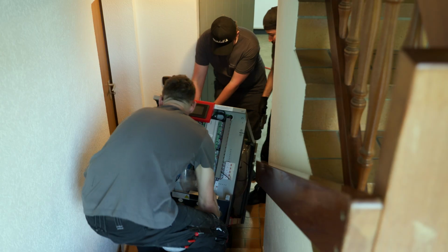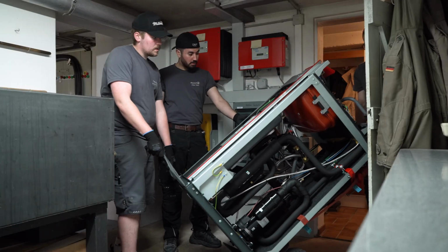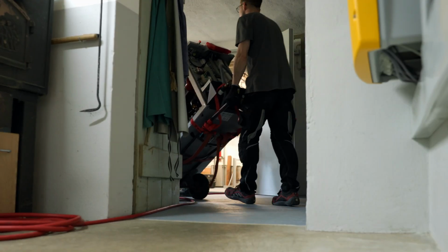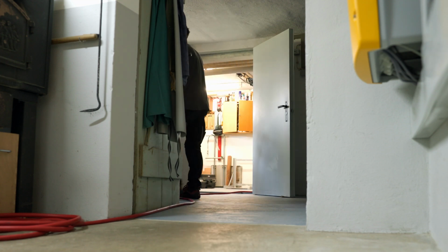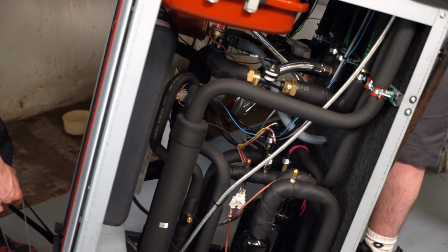The old oil heating system has been removed and the new heat pump is being installed. Technically, the new system should actually be able to provide more heat than the homeowner wants. If you install a heat pump in a building with existing radiators, then the heat pump must be able to heat up to at least 60 degrees Celsius. That's information you can easily find on the spec sheet. We won't want to heat the water that high. It's most efficient if we only operate the system at 50 or 55 degrees Celsius. That means the system needs to do more than is needed for everyday use in order to function with maximum efficiency. That would be perfect, ideal, exactly that.